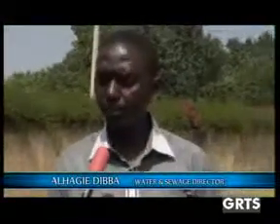For some of us that don't know how water is processed, what does the term aeration mean? Thank you. What we're trying to do with aeration is improve the pH of the water. If you like, we make it softer and more drinkable. Here in the Gambia, we have always been proud that the quality of water is good. But to meet the required WHO standards, when the water comes from our borehole, we get a pH of 6.1, and the WHO standard is from 6.5 to 8.5. So we use the aeration to build up to that level.